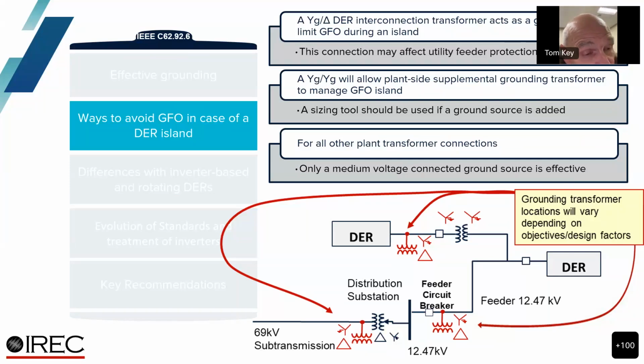So, if the inverter trips as soon as the fault event occurs, or before, right away because of its anti-islanding, there's really not an issue, but there's not much time to make a decision. So it's still a concern for utility. And you can see the picture down below. I show some different examples of locating a grounding transformer. It doesn't have to be at the DER site. The one on top is, but you can see the other ones are just somewhere else on the line.